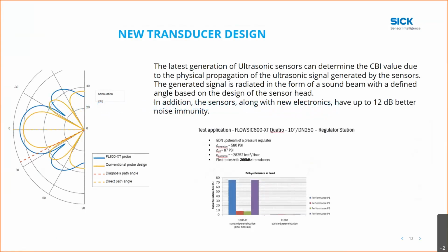Again, the new transducer design that we talked about earlier. In addition to the new transducer design, along with new electronics, you get better signal to noise, or noise immunity, with the new transducers and electronics that are now in the XT meter. There's a little snippet down here on the bottom right that shows an excerpt of some of the testing that was done with an XT meter installed 8 pipe diameters upstream of a pressure regulator, with a pressure of 580 and a differential of 87 psi, flowing at approximately 28,000 cubic feet per hour.